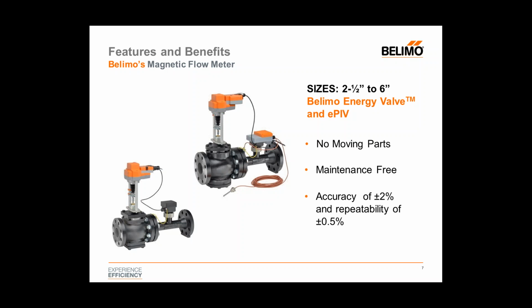They also have a very strong accuracy of plus or minus 2% of the flow and repeatability of plus or minus 0.5%. So it's a very robust sensor. It is an electromagnetic sensor that I talked about before. So this is going to be very well adapted for these particular applications.